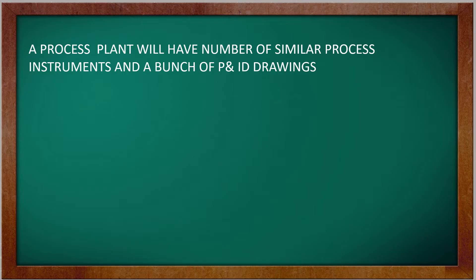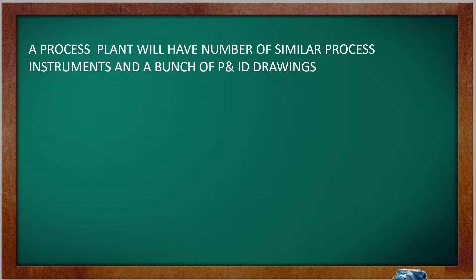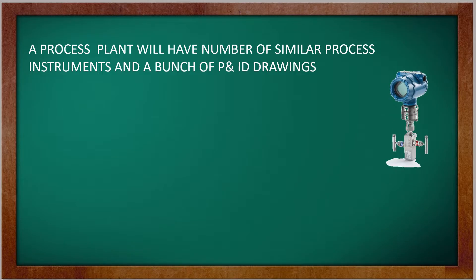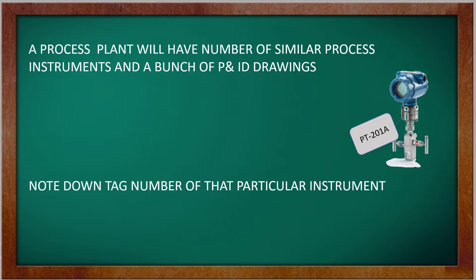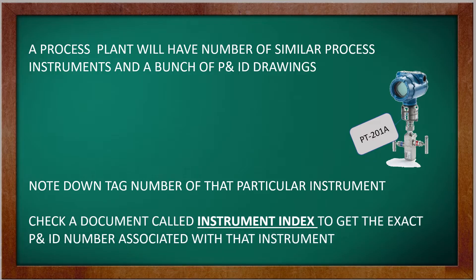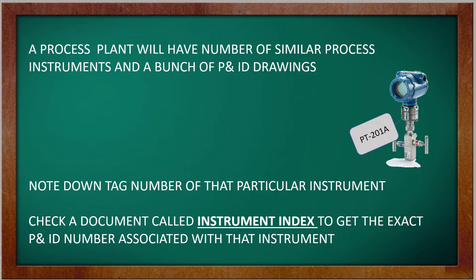A process plant will have a number of similar process instruments and a bunch of P&ID drawings. If a technician has to find a P&ID drawing associated with a particular instrument, then he has to note down the tag number of that particular instrument and check a document called instrument index to get the exact P&ID number associated with that instrument.